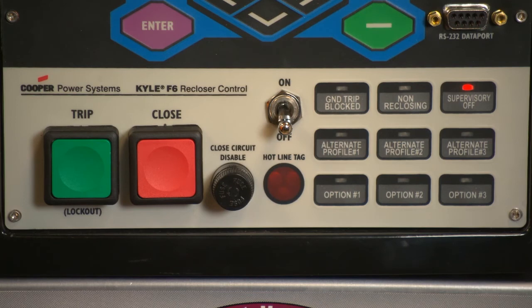Trip Lockout Push Button. The Trip Push Button provides front panel access to trip or lock out the recloser. When pressed, the Trip Push Button opens the recloser and locks out the control. The Trip Push Button operates independent of the microprocessor and is directly connected to the trip coil in the recloser. Note: in the event of microprocessor failure, the trip circuit will remain active.